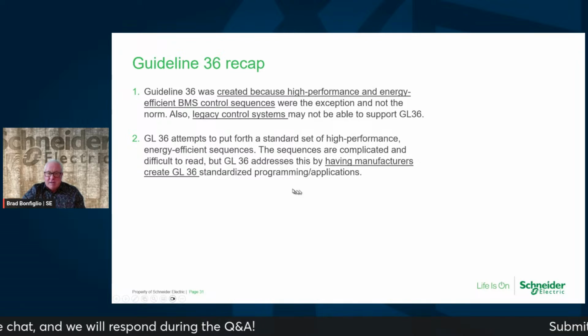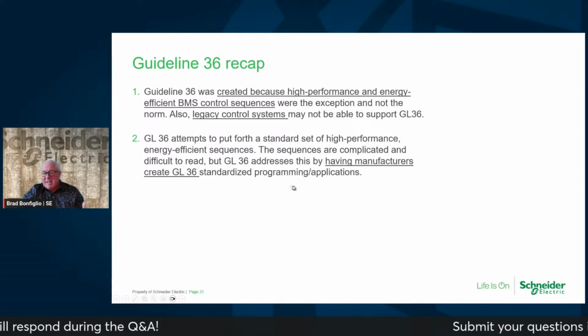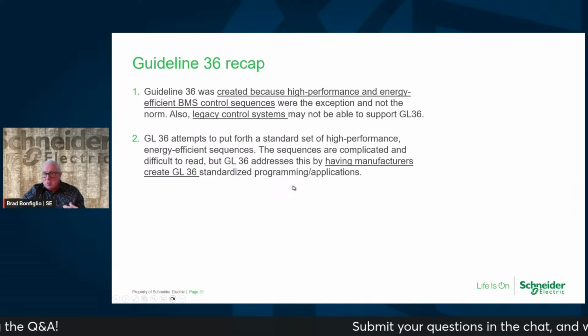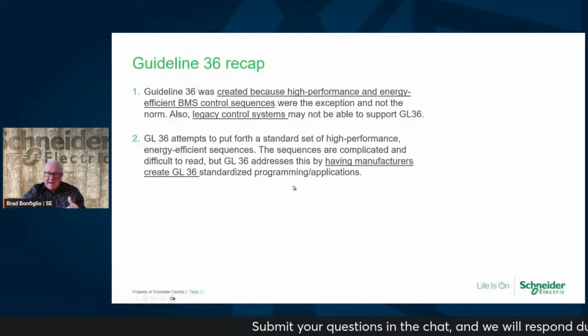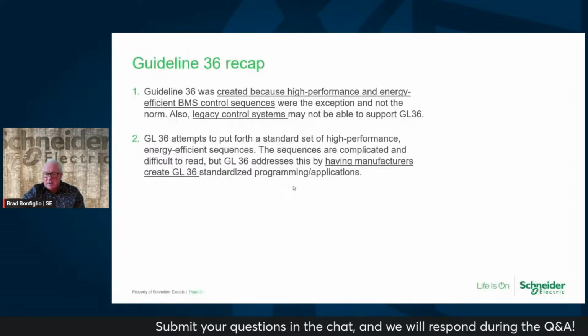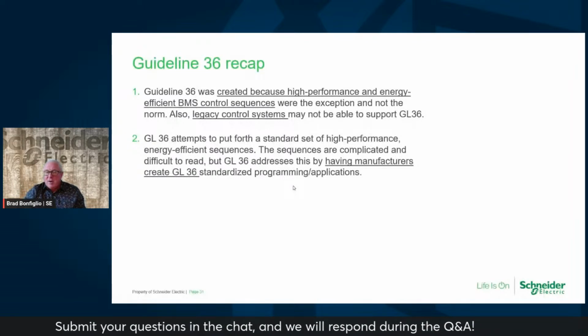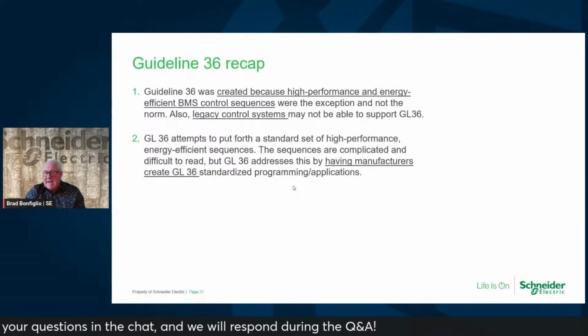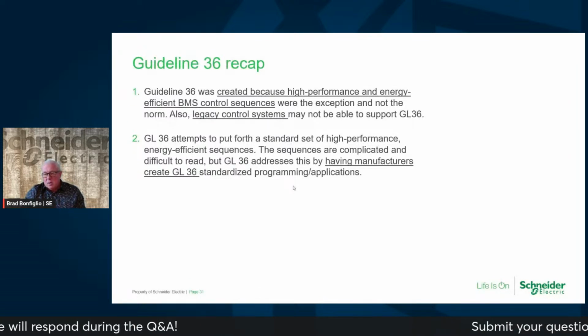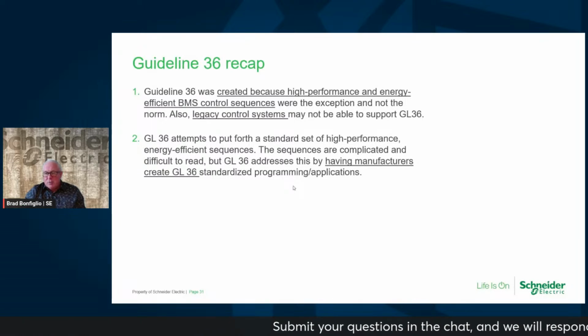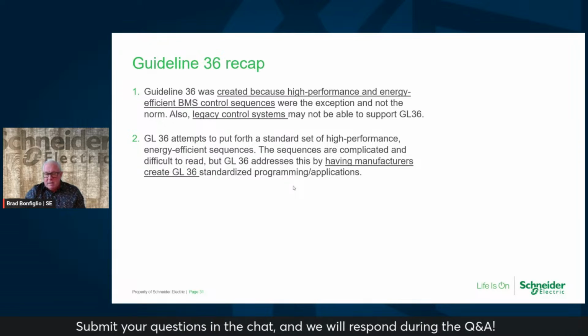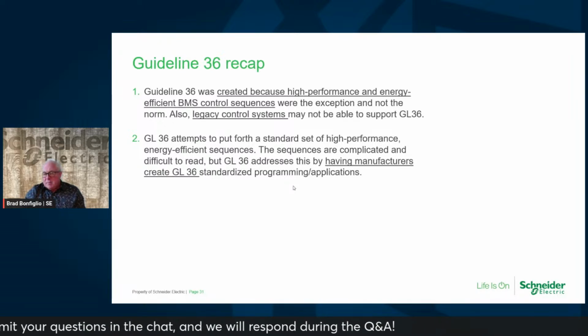Guideline 36 attempts to put a standard of a high performance sequence so that the manufacturer actually provides this to the integrators, okay, and factory offices. That way they're not having to add a cost on the job itself. You'll get where when you start seeing Guideline 36, hopefully you'll get some references to which standard they're going to follow: the trim and response, the economizer, the fault detection, the alarm mitigation.